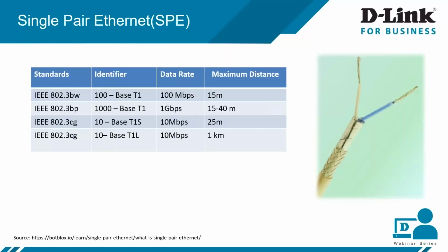Now let us understand some single pair Ethernet basics. The IEEE specification for 10 megabit per second is 802.3cg, which supports full duplex data communication up to 1000 meters at 10 megabits per second. Then there is IEEE 802.3bw, which supports full duplex data transmission over a single pair, providing up to 100 megabits per second for cable up to 15 meters. So what is the application?